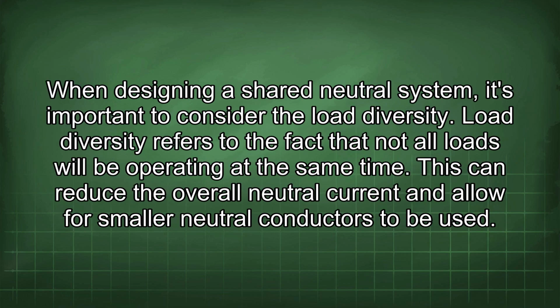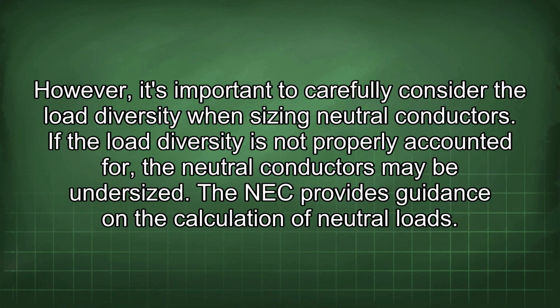When designing a shared neutral system, it's important to consider the load diversity. Load diversity refers to the fact that not all loads will be operating at the same time. This can reduce the overall neutral current and allow for smaller neutral conductors to be used. However, it's important to carefully consider the load diversity when sizing neutral conductors. If the load diversity is not properly accounted for, the neutral conductors may be undersized.